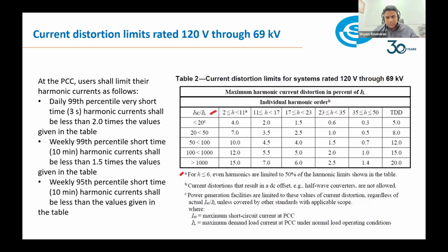From the definition I showed in the beginning, for TDD calculation we use IL, so the same IL is taken here also. Another parameter shown here, which I marked in red, is ISC by IL. ISC, as shown in the definition, is the maximum short circuit current at PCC. But let me put it to you very frankly, the majority of my customers do not know what this ISC value is.